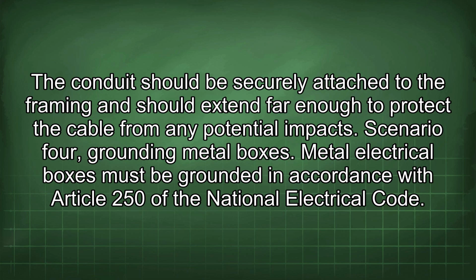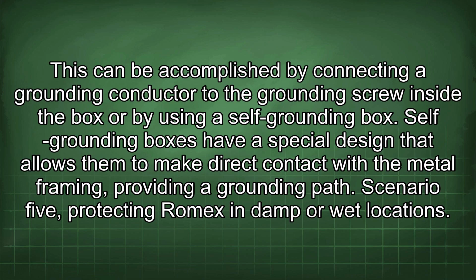Metal electrical boxes must be grounded in accordance with Article 250 of the National Electrical Code. This can be accomplished by connecting a grounding conductor to the grounding screw inside the box or by using a self-grounding box. Self-grounding boxes have a special design that allows them to make direct contact with the metal framing, providing a grounding path. Scenario 5. Protecting Romex in damp or wet locations.